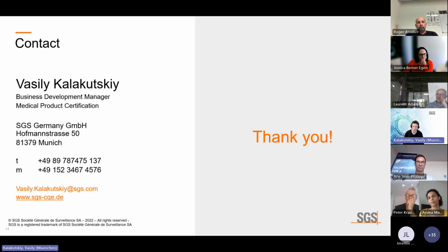And this address will also be used for the post-market surveillance, for the complaints. Something shall be put on the label. Even for software, there is a label. So basically in the menu, there is an about section, and there you provide the information about your product. So the address that is written there is theoretically the address where the audit may take place.